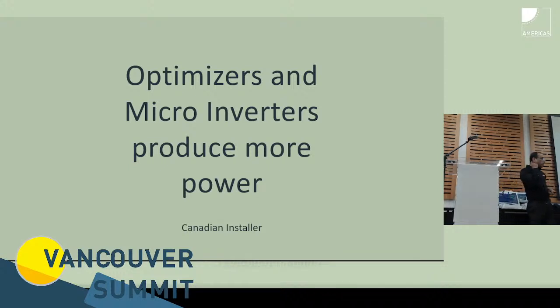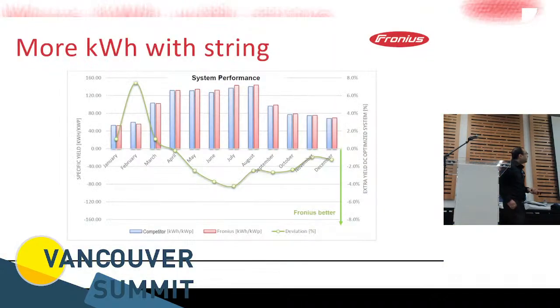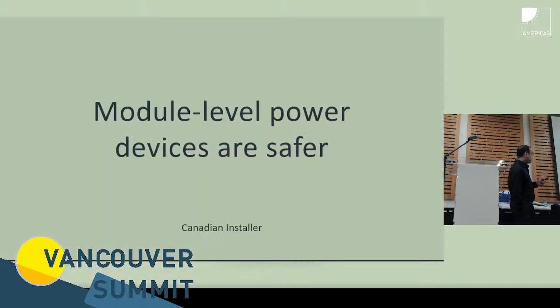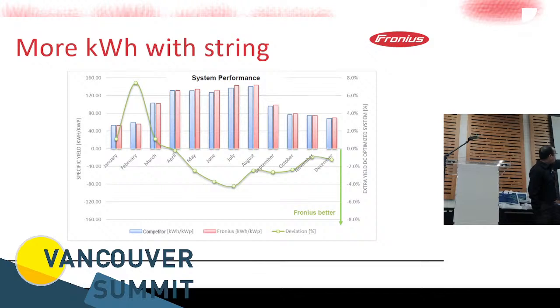So all I wanted to make the point is that when it comes to a fair comparison between optimizers and string inverters or microinverters, it's not as cut and dry as it's made to seem. This is a comparison we did on our Fronius offices, and you'll see that microinverters do outperform string inverters in deep winter—or rather, only in the parts of the year where you're actually buried under snow.